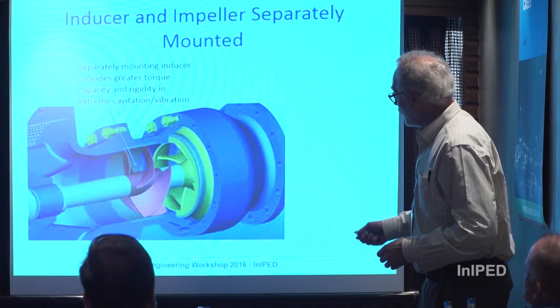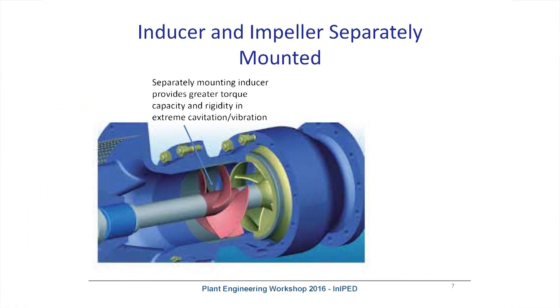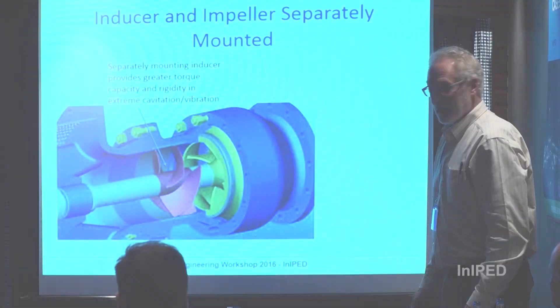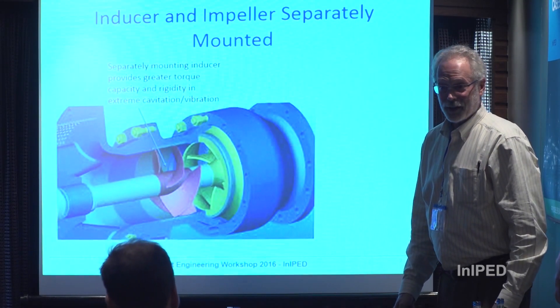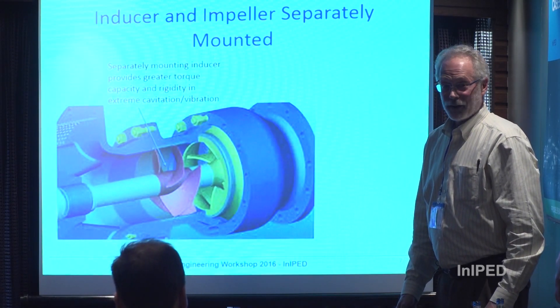In those cases you want to move to an inducer keyed directly onto the shaft, giving you the full torque-carrying capability of the shaft. Using a vertical turbine pump as an example, the inducer gets keyed to the shaft — very high torque capability — and it's retained so it's not going anywhere until there's no more vane left to pump.